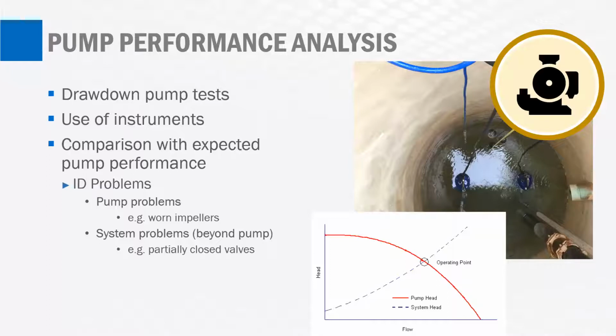And that total dynamic head is very important for us to understand along with the flow, so that we can see whether or not the pump is operating on its curve. You can see the pump curve there to the right in red and the operating point circled. Well, that operating point may not be where that pump is operating. Maybe it's operating to the right of that operating point, which means it's operating at a higher flow than originally intended. Maybe it's operating to the left of that operating point, which may mean that you have obstructions in your force main.